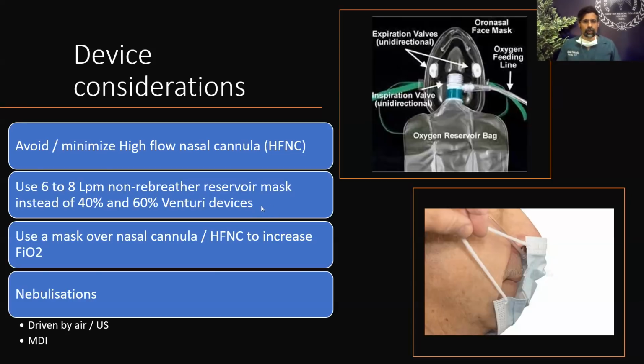The next consideration is to not use 40 and 60% Venturi devices, because these use 12 and 15 liters of oxygen to run. And the same FiO2s can be delivered by using non-rebreather reservoir bags, which have valves to prevent rebreathing. And they don't waste oxygen during expiration, because during expiration, the oxygen that's coming in from the inlet fills the reservoir bag, which is then breathed in by the patient during the next inspiration. And so at 6 and 8 liters per minute, you can actually get 60 and 80% FiO2. So it saves oxygen when you switch from high level Venturi to NRM masks.